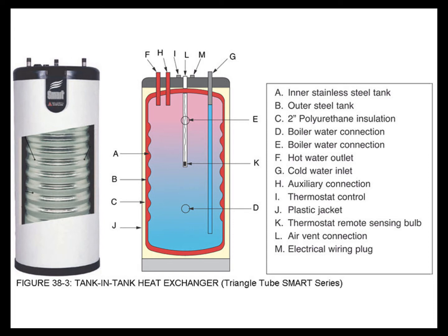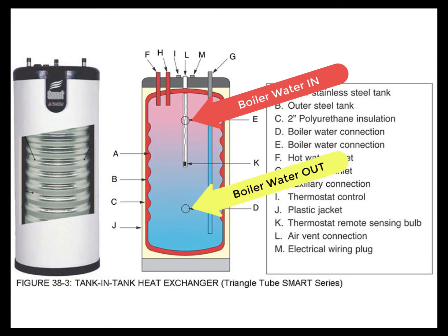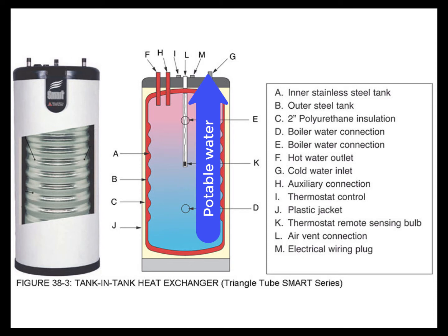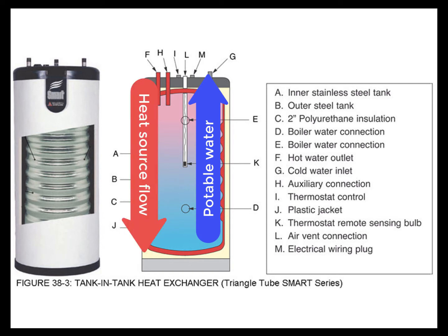Per the manufacturer's instructions, this is also a counterflow type of heater, with the hot water being introduced to tapping E on this drawing, and then the return water going back to the boiler through tapping D. So it would be a situation where the potable water is going in the exact opposite direction as the heat source water.